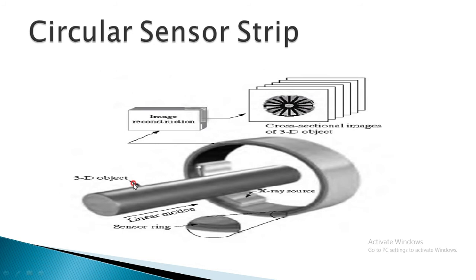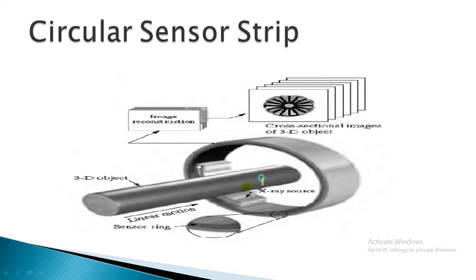In this arrangement, we will be having a 3D object, a rod like this. This 3D object will be having a linear motion, that is front and backwards. This would move in a circular motion. On this circular thing, we will be having an x-ray source, and that x-ray source will be emitting, and the same x-ray will be collected by the sensor which is there on the inner part of this thing.